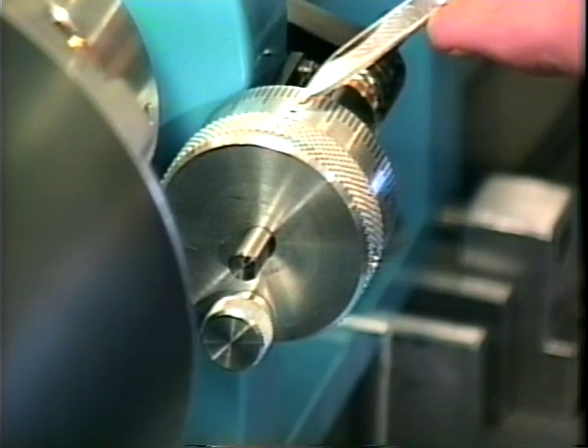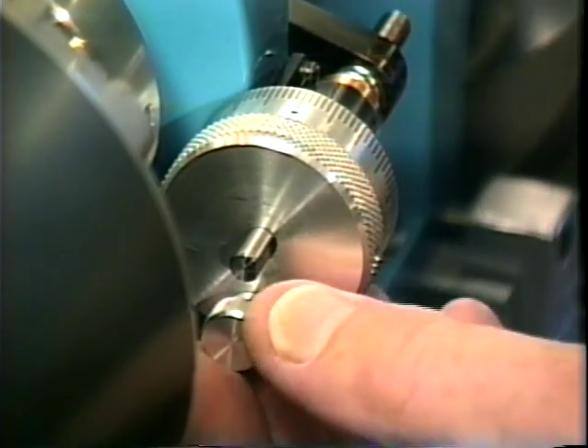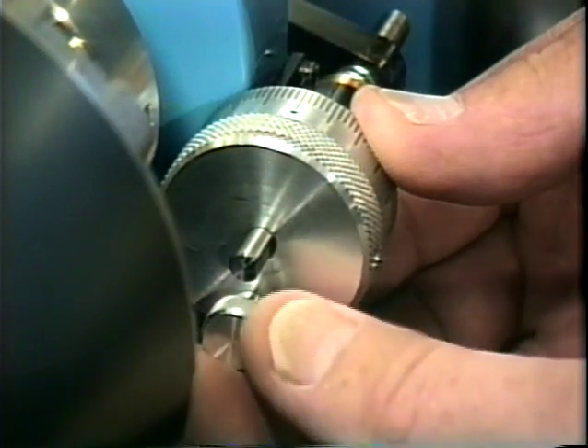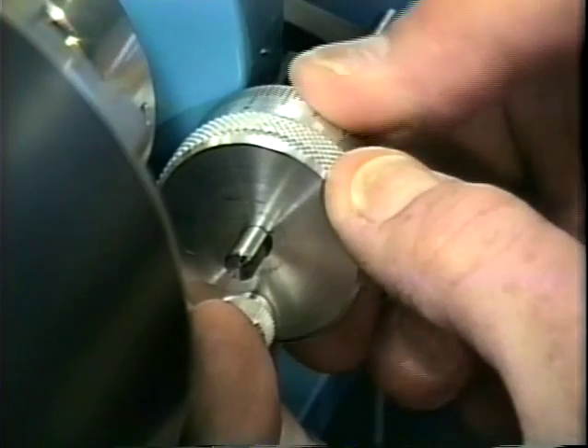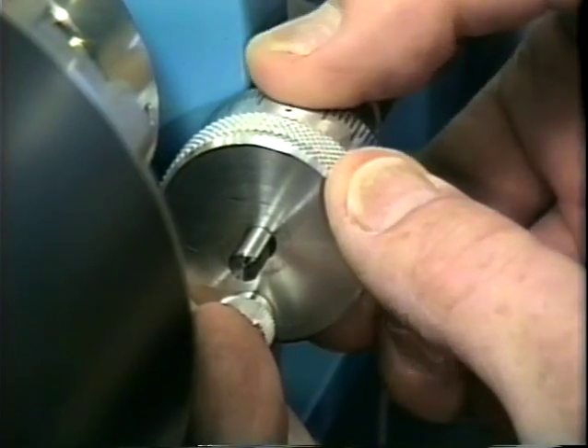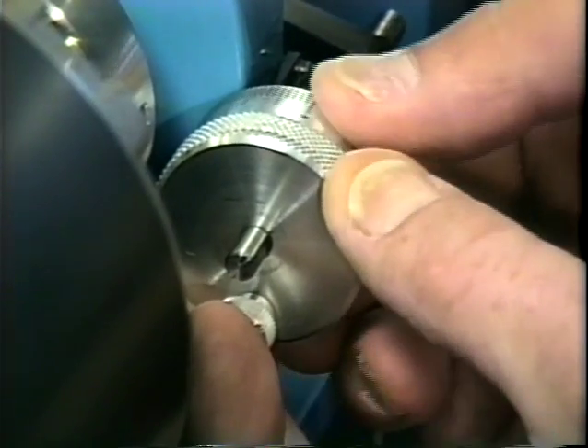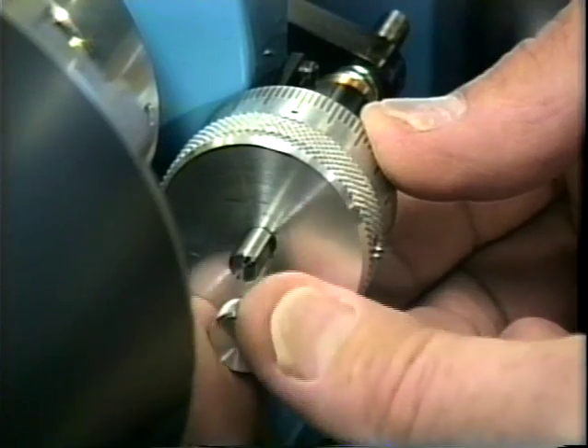The micrometer has a red reference dot on the dial. The dial is otherwise graduated in 6 micron increments. To set the reference dot, loosen the locking knob, rotate the dial so it lines up with the pointer on the micrometer, then relock the knob.